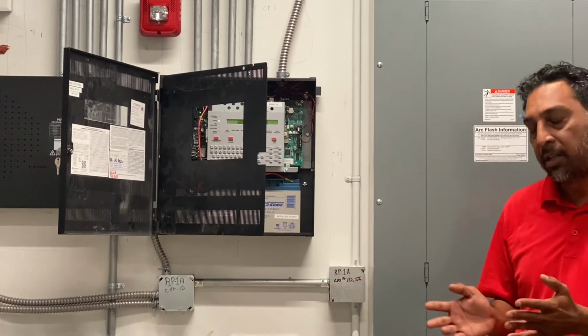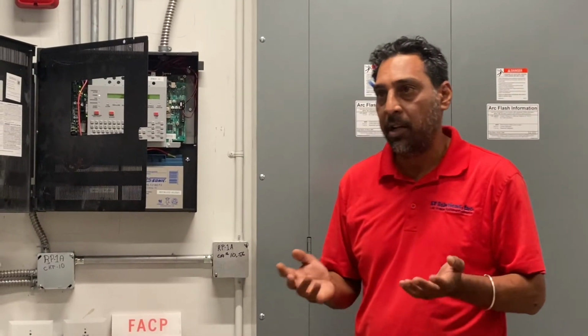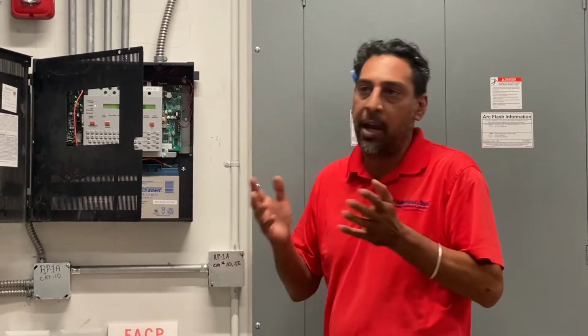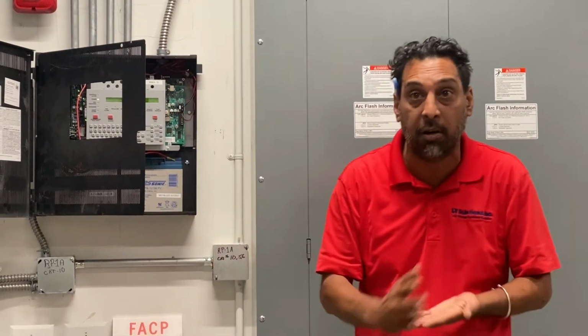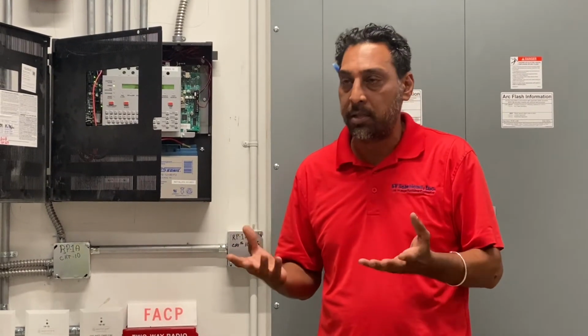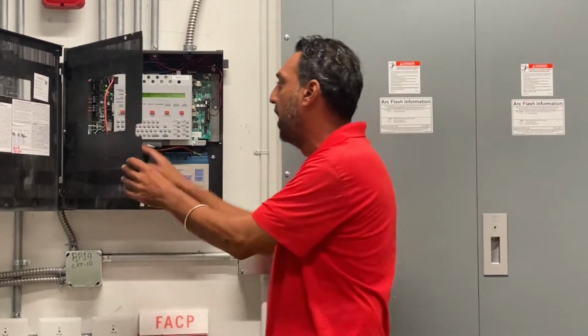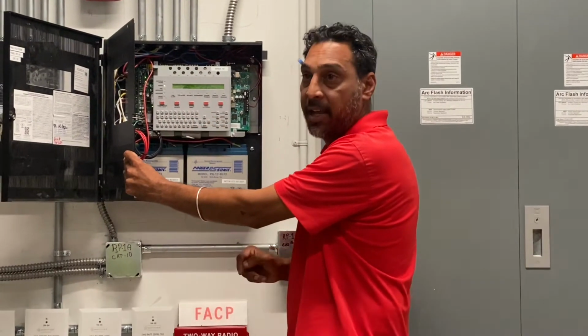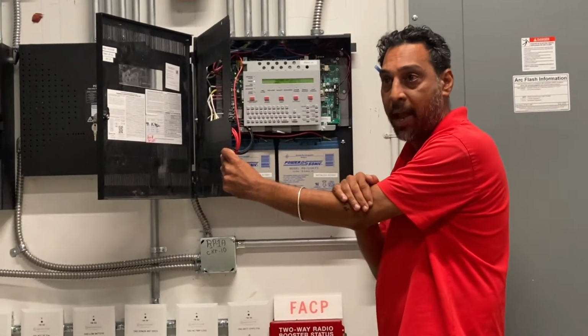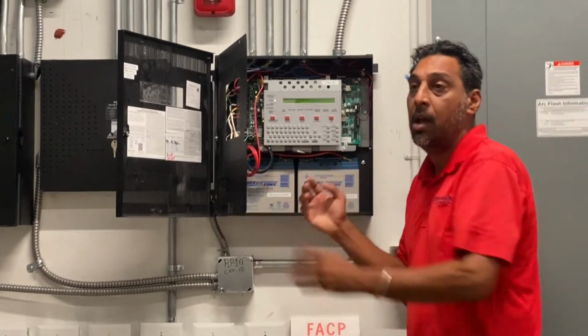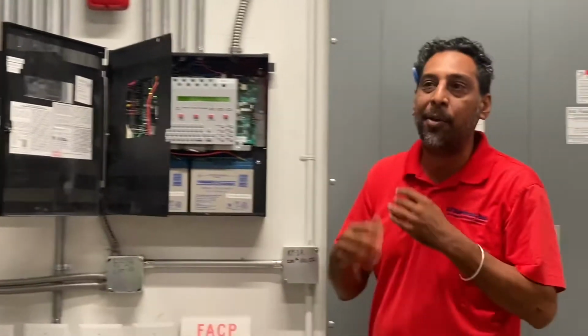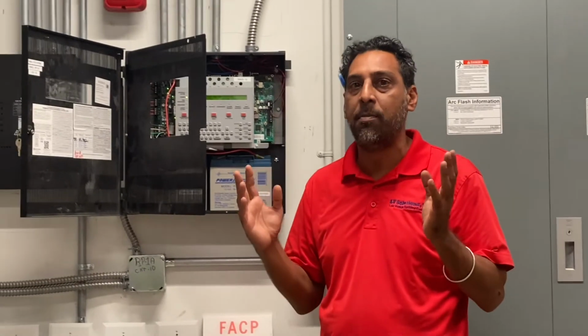So if the duct detector comes into supervisory, you'll get an active latch supervisory. It'll say duct, and it'll tell you air handler 1, 2. On some of the duct detectors, we have them in the tenant space on third floor, so we have the description so you guys know exactly where they're at. Once the particles clear out, you hit acknowledge, and then you can hit reset. If that duct detector goes clear, then the panel will go normal, and within about 30 seconds, your air handler will turn back on.